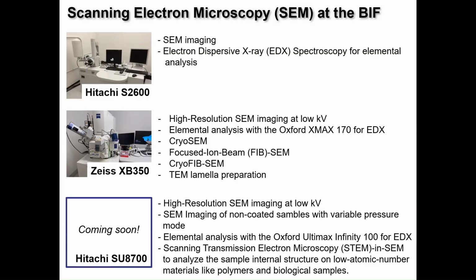In the coming months, we are going to install the Hitachi SU8700. This is another SEM. We can do high resolution SEM imaging at low kV. Also, it has a variable pressure mode. So we tested some non-coated samples, and we can get a very good high resolution image using variable pressure mode. Also, it comes with EDX capability, and we will have a STEM detector, so we can put TEM samples in and see the internal structure of low atomic number materials like polymers, carbon nanotubes, and biological samples.